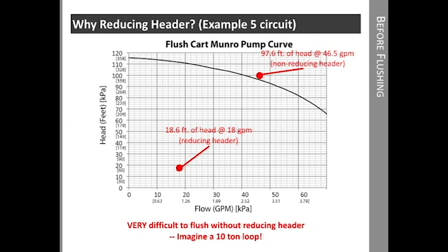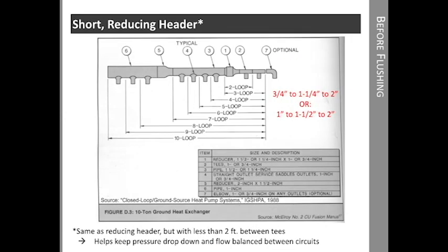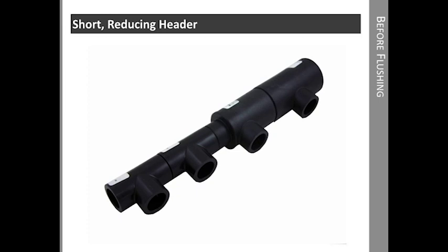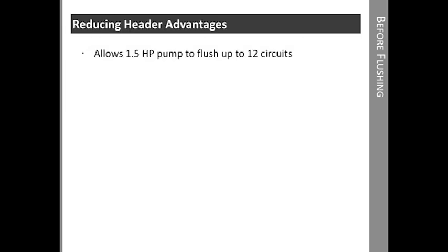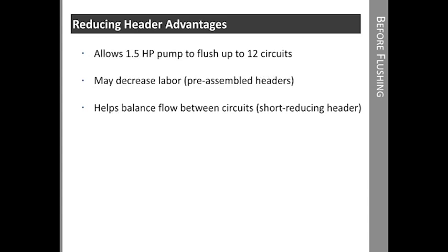A short reducing header is another concept we should discuss. It's still a reducing header, but the distance between T's is less than two feet. This helps keep pressure drop down and also helps maintain balanced flow between circuits. This is a picture of a pre-fabricated short reducing header for a five circuit system. As you can see, the T's are very close together. So even though the last two circuits are three quarter inch, the distance is so short that the pressure drop is negligible. There are some big advantages to a reducing header: we can flush up to 12 three quarter inch circuits with a one and a half horsepower pump. It can really reduce the labor, especially with pre-assembled headers. And it helps balance flow between circuits if we take advantage of the short reducing header.